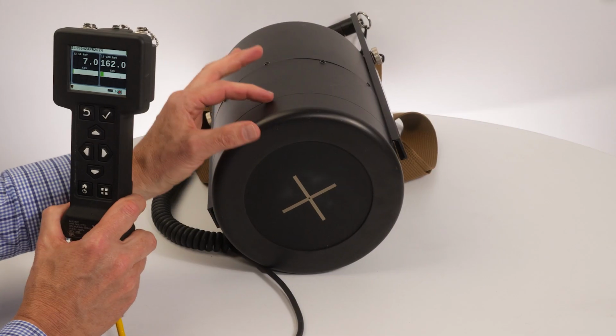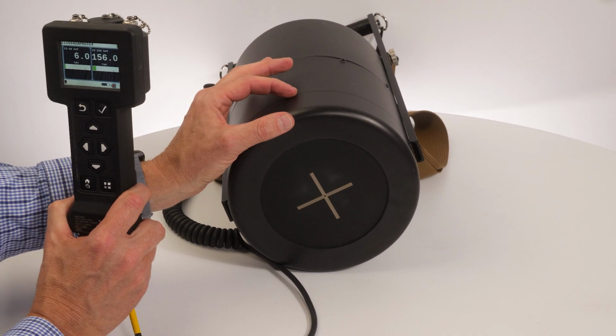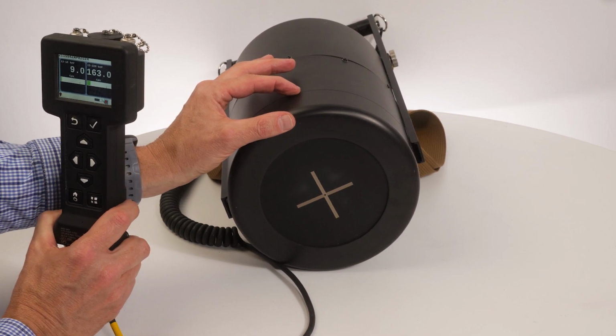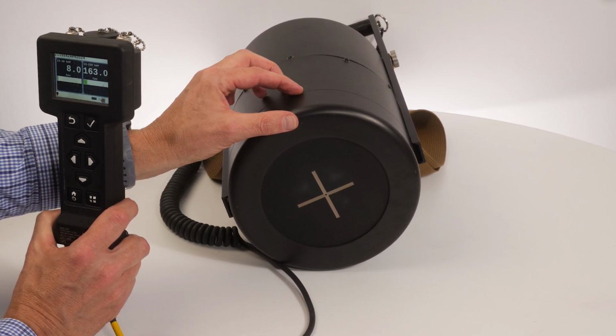The FIDLER Probe's detector is set back 2 inches from the bottom face of the probe due to the addition of thermal insulation. Keep in mind these 2 inches when determining a distance between the detector and surfaces being surveyed. Never place the FIDLER Probe in direct contact with a suspected radiological surface to prevent the face of the probe from becoming contaminated with radioactive material or other material that would lead to shielding and obscure the readings.